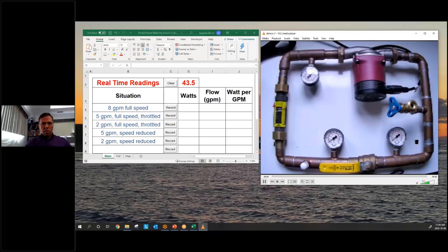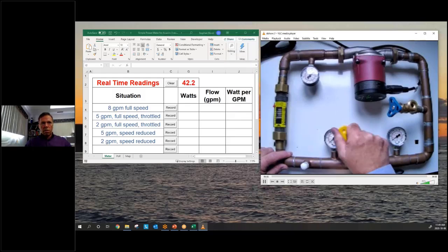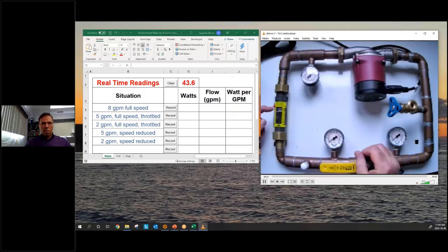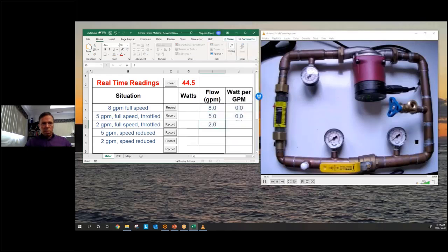Okay, and ultimately you can see my little flow meter here. It's just a little plunger, and as you can see I'm varying the flow, and this is my valve. So I've got 3 points. I have 8 gallons a minute, 5 gallons a minute, and 2 gallons a minute. So that's what we're going to do. We're going to try to achieve different flows: 8 gallons a minute, 5 gallons a minute, and 2 gallons a minute. Right now, I'm doing it right at the 8 gallons a minute. The valve's open, and we're using about 44.5 watts.